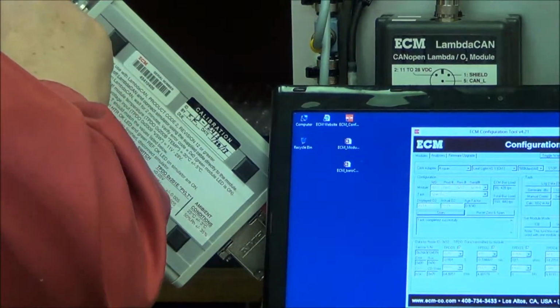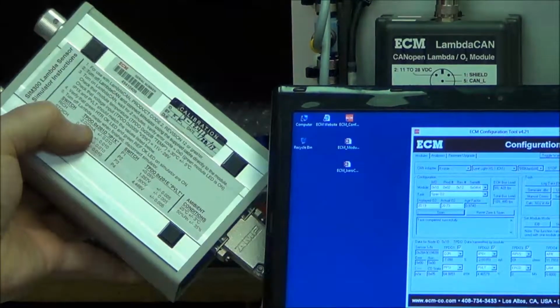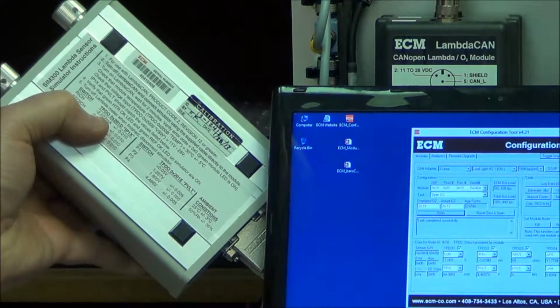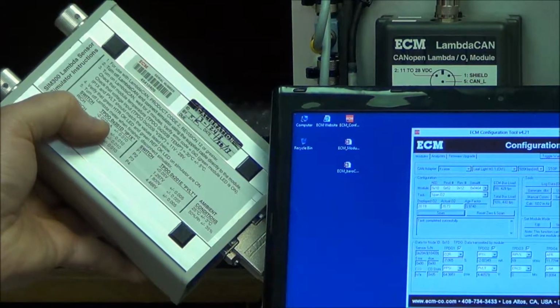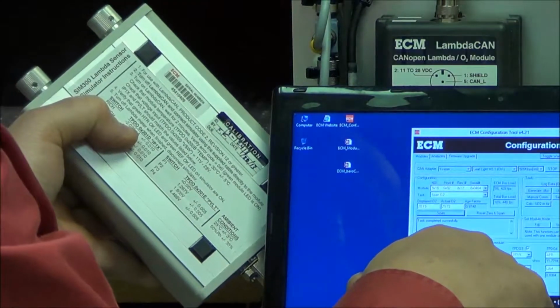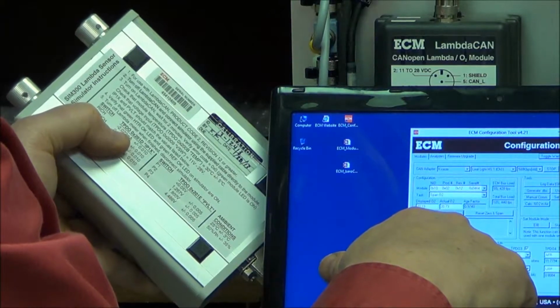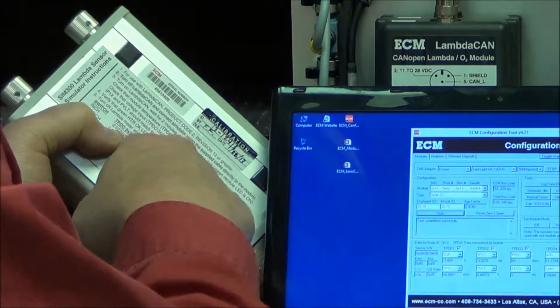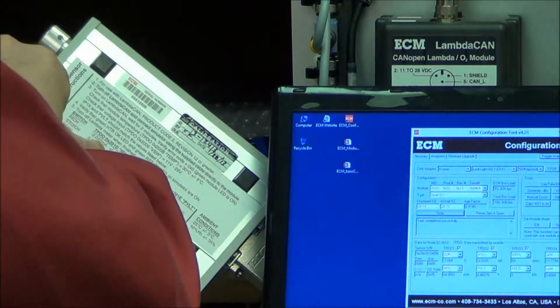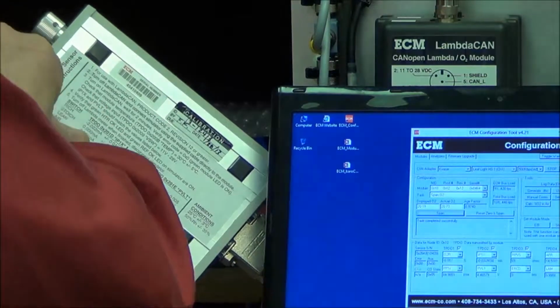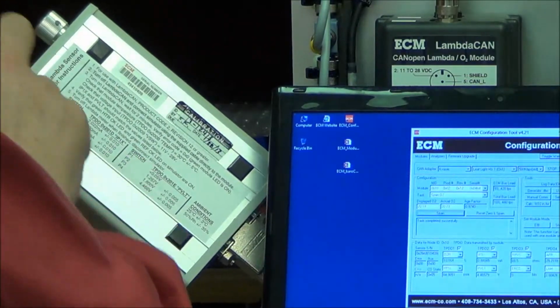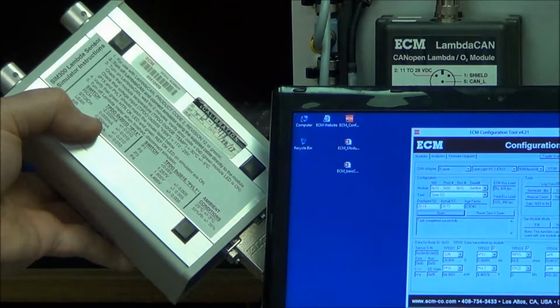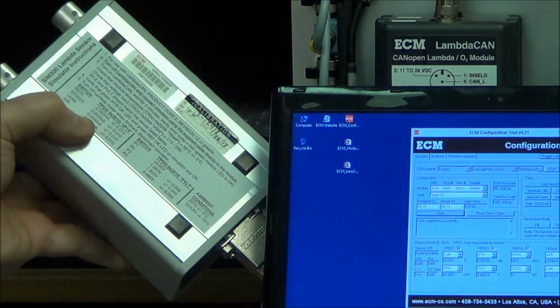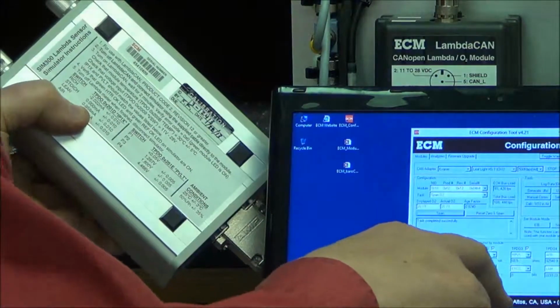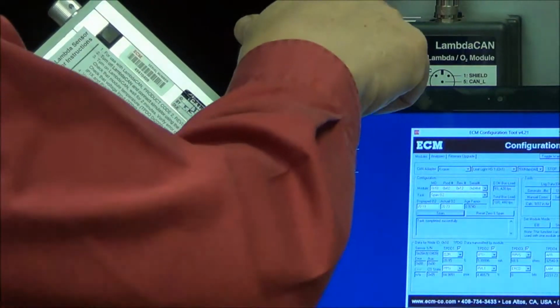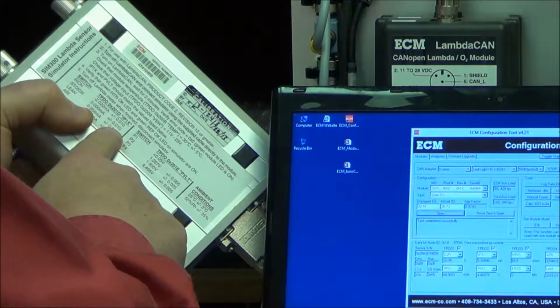So click it on to rich Lambda, which here it says should output minus 2.02 milliamps of IP1X. That's the fundamental current coming out of the sensor, called IP1X. So you look down here at the parameter, IP1X, it says minus 2.023. I want 2.022. It's plus or minus 1/100th of a milliamp. It's within spec. Then you repeat it for stoichiometric, which is 0 milliamps. Lean, which is 0.956 milliamps. Air, this is simulating a 6 milliamp NTK sensor, should be 6 milliamps in air. And the displayed current output from the LambdaCAN should be the same from this precision current source.